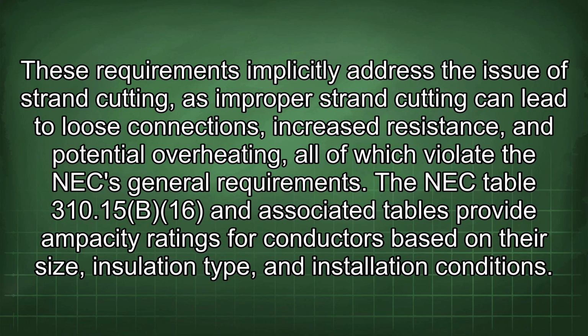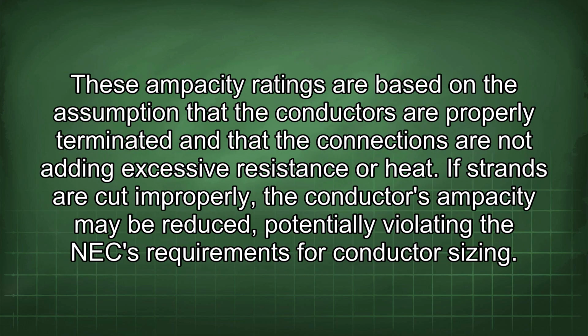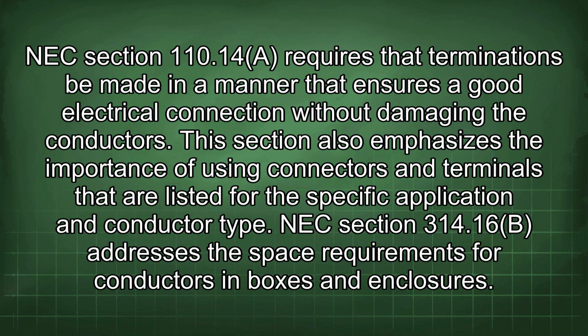The NEC Table 310.15(B)(16) and associated tables provide ampacity ratings for conductors based on their size, insulation type, and installation conditions. These ampacity ratings are based on the assumption that the conductors are properly terminated and that the connections are not adding excessive resistance or heat. If strands are cut improperly, the conductor's ampacity may be reduced, potentially violating the NEC requirements for conductor sizing. NEC Section 110.14 requires that terminations be made in a manner that ensures a good electrical connection without damaging the conductors. This section also emphasizes the importance of using connectors and terminals that are listed for the specific application and conductor type. NEC Section 314.16(B) addresses the space requirements for conductors in boxes and enclosures.